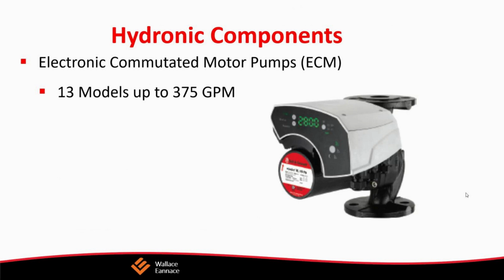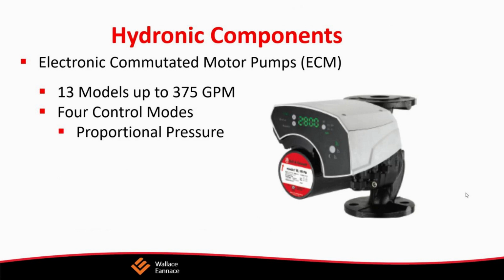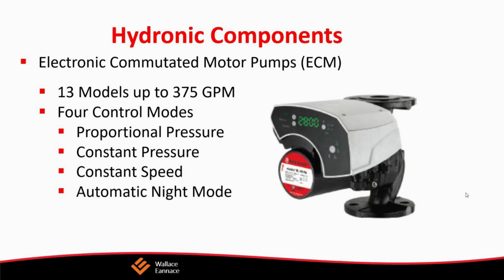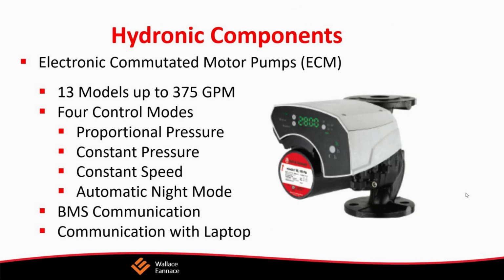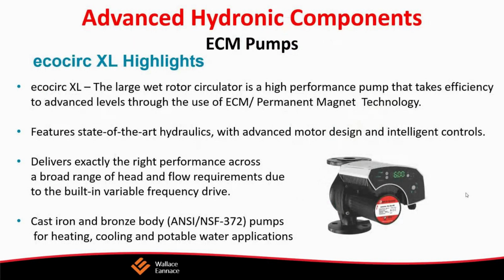A check valve is included in the box, and it also comes with an insulation shell. The ECM EcoCirc Plus 2018 comes with all its standard features found in the EcoCirc 2018 Plus. It has Bluetooth communication, and what's really useful is a 0 to 10 volt input, which allows you to connect to any boiler that has a 0 to 10 volt signal, and will allow the pump to modulate based upon that input signal. It also has temperature control, and also has an eAdapt auto learn and night mode.